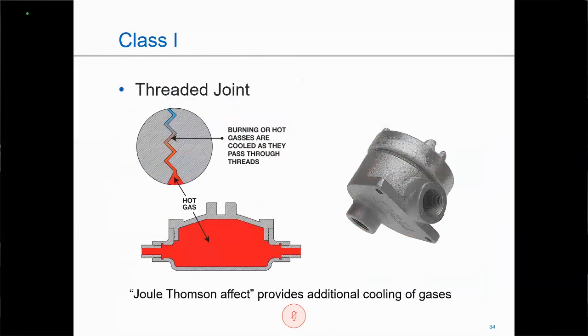So I have a particular unit that is a threaded flame path. Here, this unit is going to contain the explosion, and the time it takes for the gases to pass over the threads, with the metal acting as a heat sink, is going to cool those gases and then harmlessly release them back out to the atmosphere.